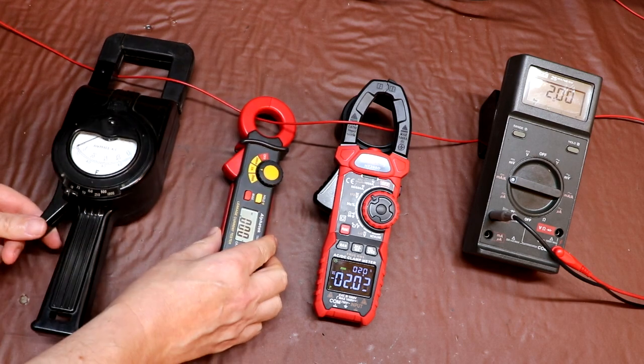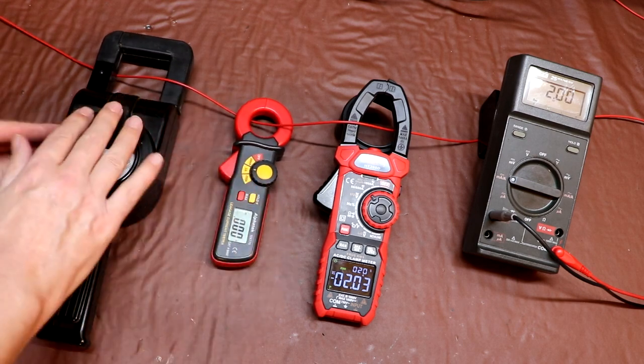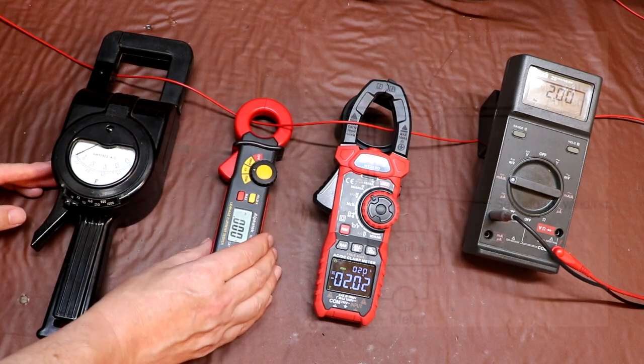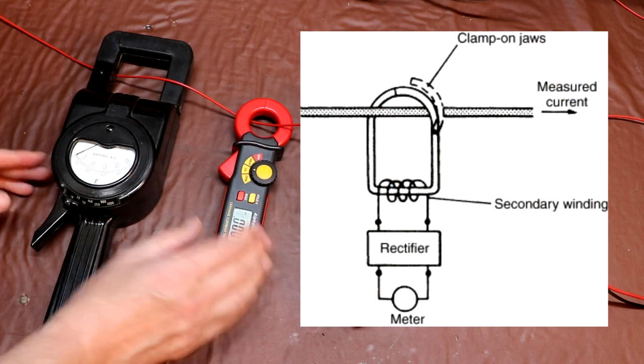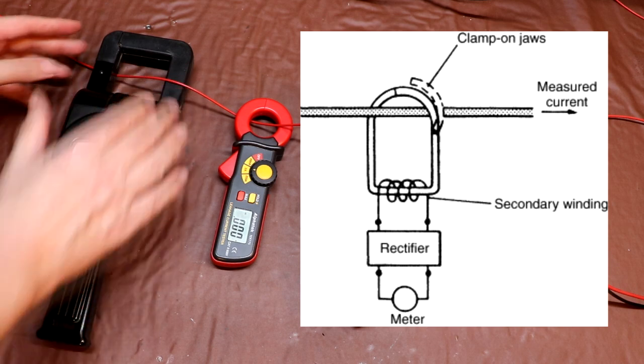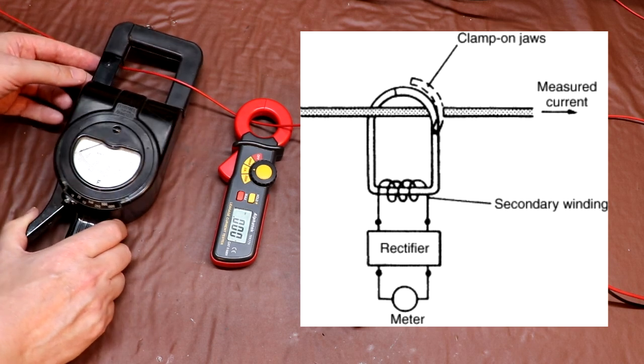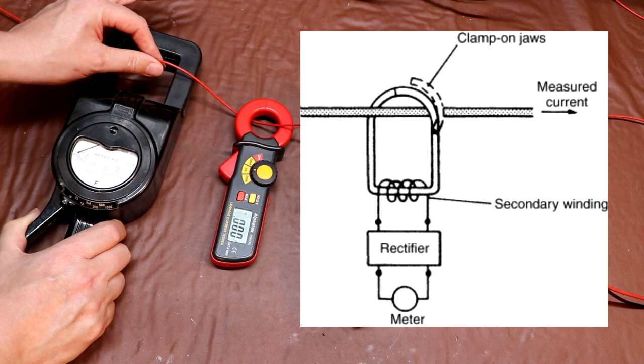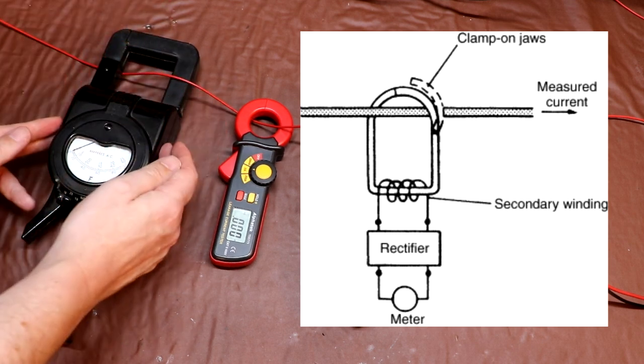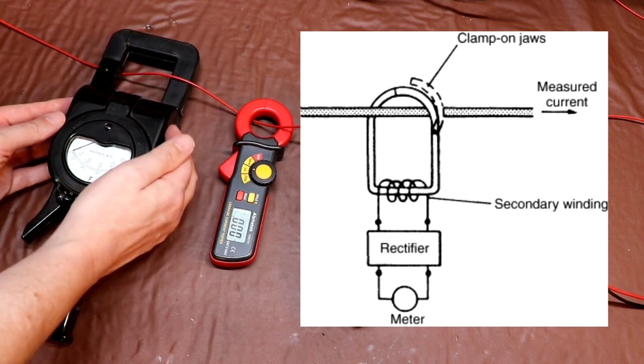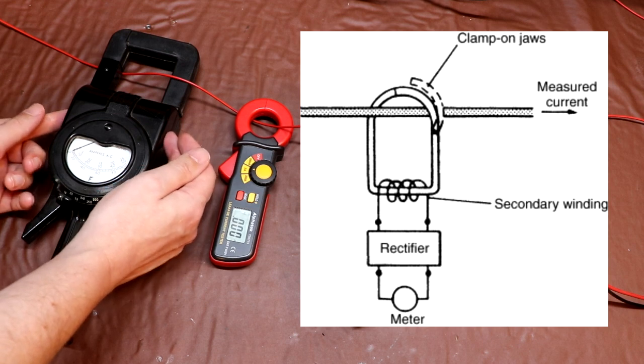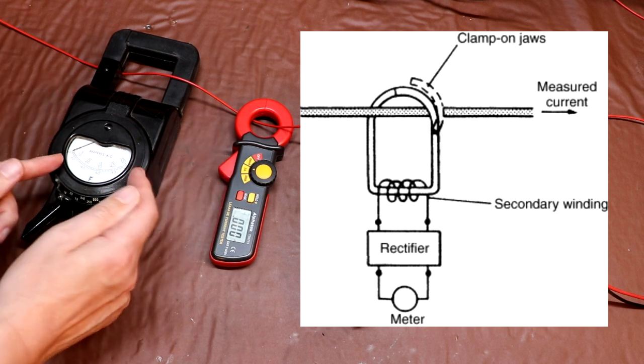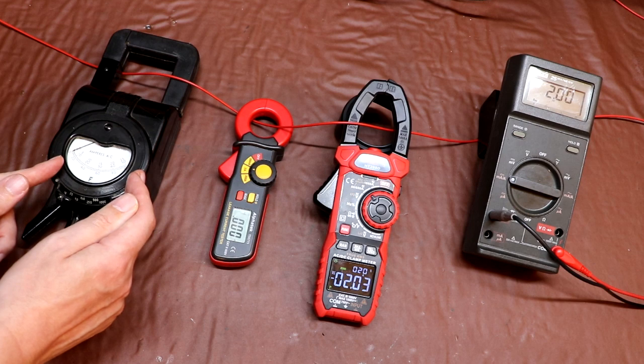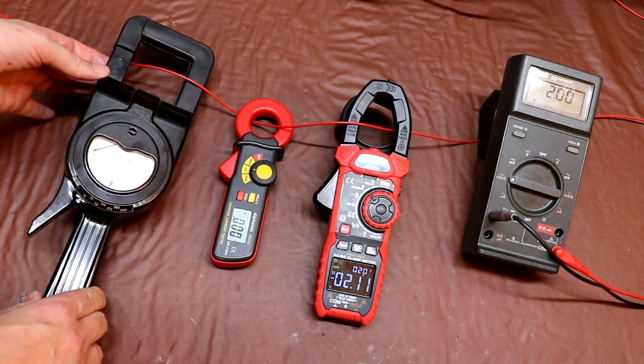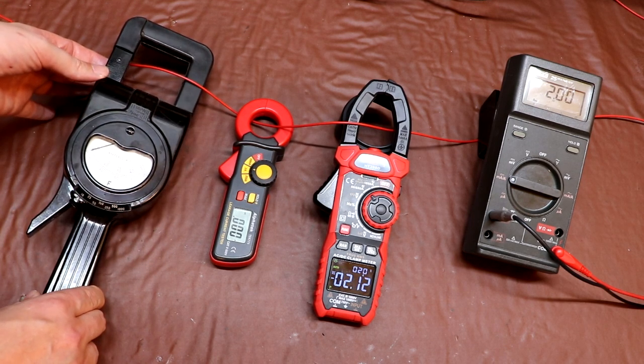Now although at first glance it might not be obvious, both of these instruments are what I would call transformer based. So you've actually got a transformer, and in this case let's look at this one. So we've got a transformer and we've got one turn on the primary, then the secondary part of the transformer, which is inside the instrument here, inside the box, we've got another coil of wire, and that coil of wire is actually just connected to an ammeter here. Now I'm sure that all of you know that transformers, they won't actually work with DC.